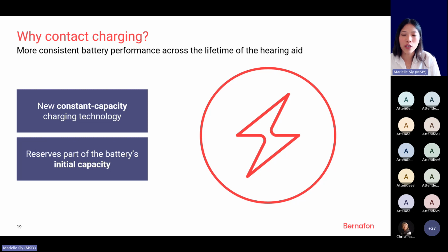And the reason why there are so many improvements in this rechargeability is the fact that we actually changed our approach from inductive charging to contact charging. And this allows more consistent battery performance across the lifetime of the hearing aid. Now, I'll explain why we did this change. So with rechargeable batteries, battery capacity will drop over time, right? So that means that the user or the client may start hearing the battery low warning at the end of the day after using the hearing aid for a few years.